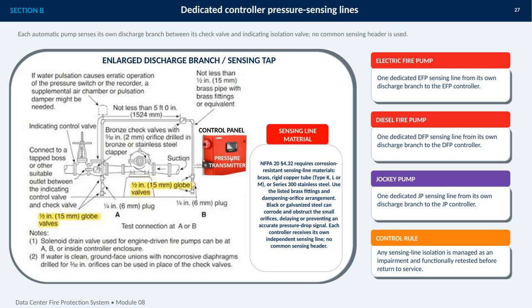This section addresses dedicated controller pressure sensing lines. The key principle is simple. Each automatic pump senses pressure through its own independent line. The electric fire pump has one sensing line from its discharge branch to the electric fire pump controller. The diesel fire pump has a separate line to its own controller, and the jockey pump has a third dedicated line to the jockey pump controller.